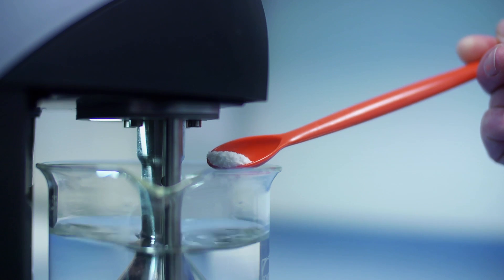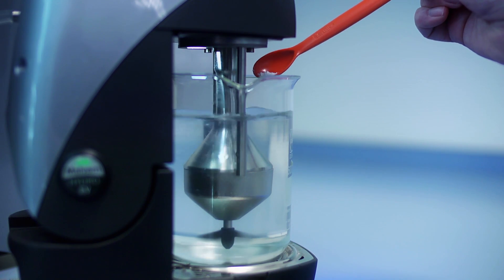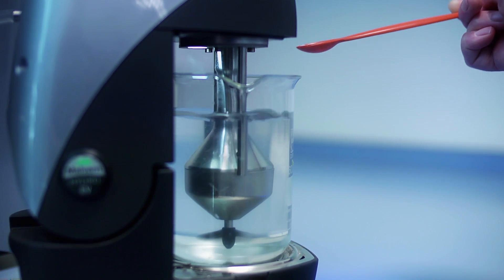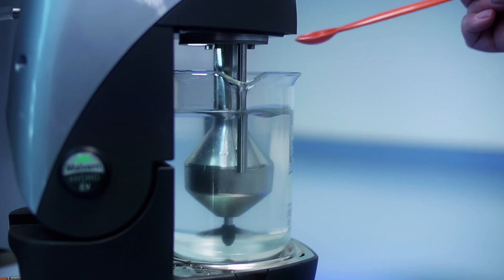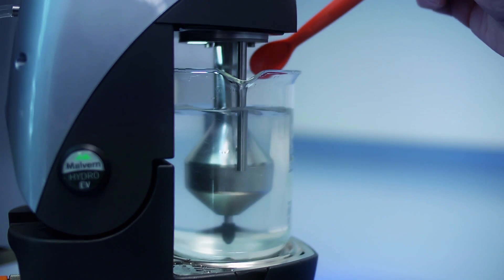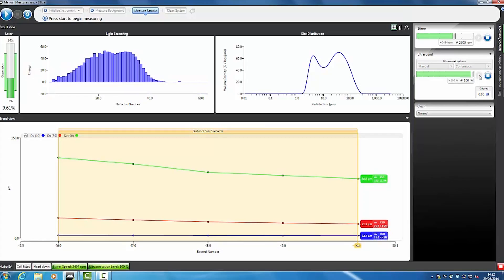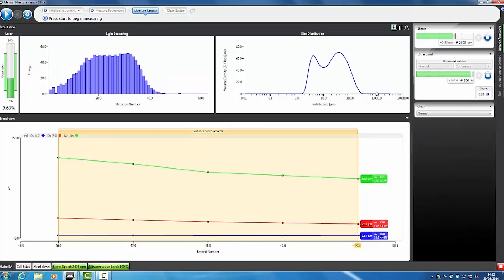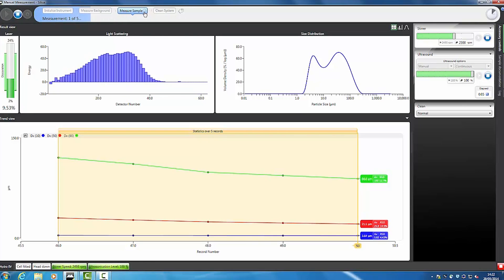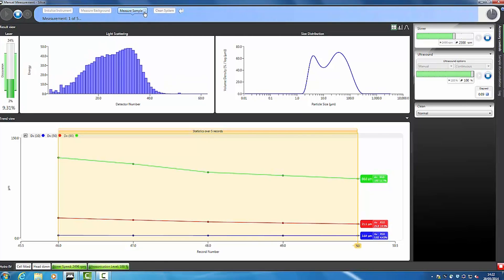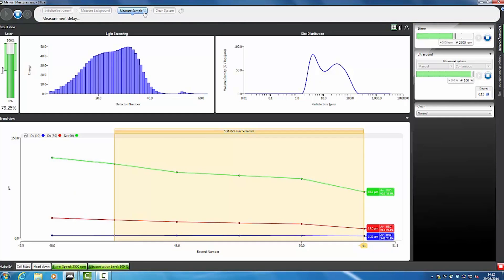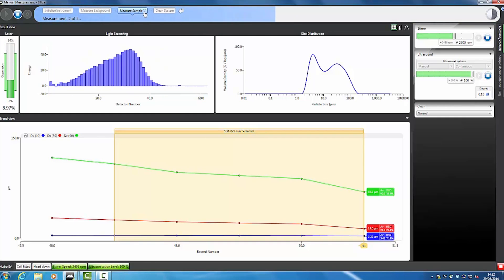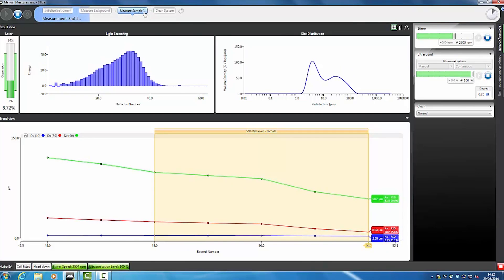Method development requires a user to select the optimum dispersion settings to achieve stable, reproducible results. Live feedback of the dispersion process quickly shows when the sample concentration is suitable for measurement. The process of sample dispersion during stirring and the application of inline sonication can then be followed within the measurement manager.